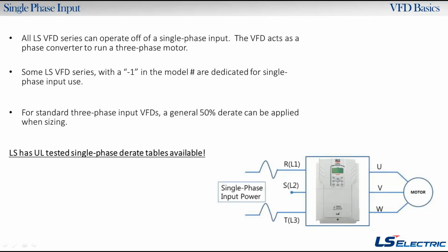I think we do that up to like 3 horsepower or so for the S100, the M100, where there's a -1. So you could order a 3 horsepower drive, run your single phase in, and run your 3-phase out, and you're good for 3 horsepower. Something else to note is we could always run single phase in, but we don't run single phase out. We only run 3-phase electric induction motors, and then we could also run 3-phase permanent magnet motors on the S100, but always 3-phase out.